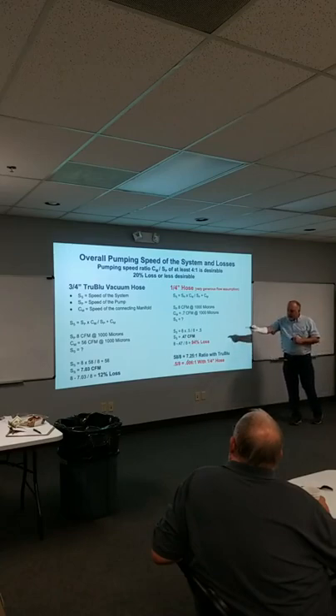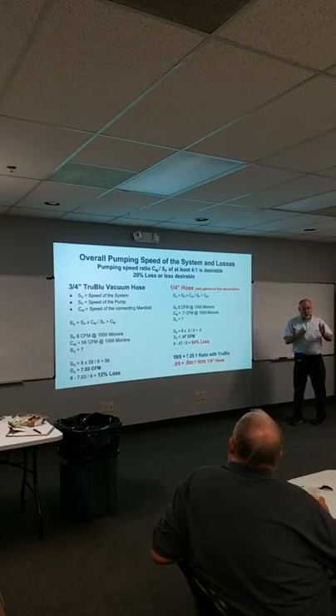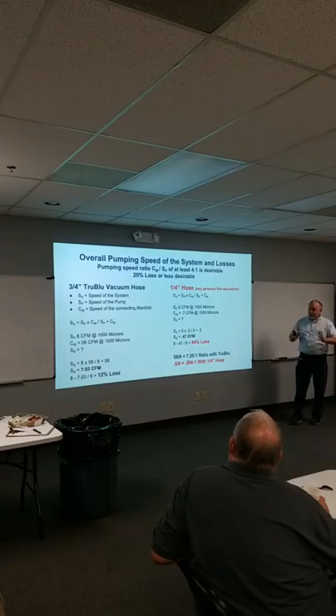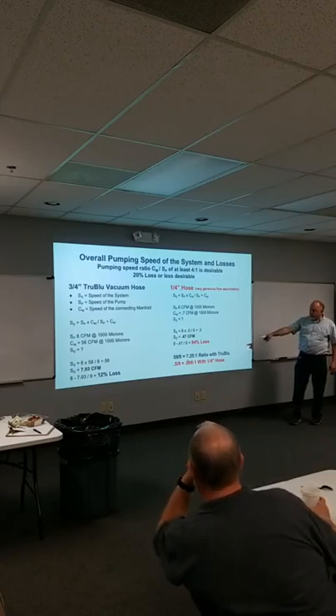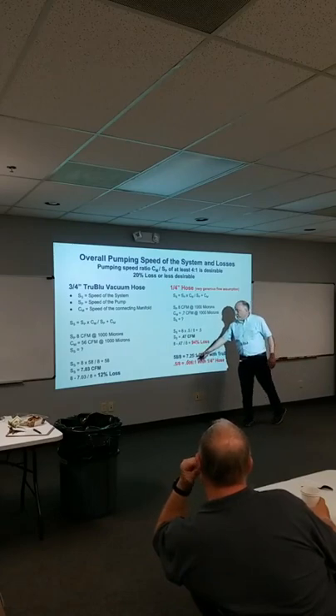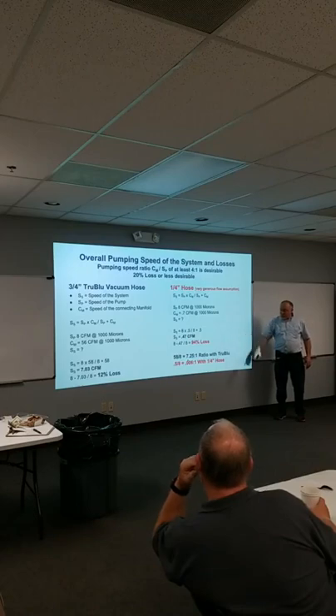Statistical formula. So basically, if we were to take a, and you want to have a pumping speed of at least 4 to 1, right? There's always a loss. As soon as you hook up a vacuum hose to a vacuum pump, there's a loss, period. Can't stop it. The pumps are all rated at free flow, okay? So that 8 CFM pump is 8 CFM at free flow. So down here, I just did the math here, and if I hook up, to an 8 CFM pump with a true blue hose, I have about a 12% loss, which sounds substantial, but that is a ratio of 7.25 to 1. So way over 4 to 1, right? 4 to 1 is desirable, but it's 58 to 8 ratio or 7.25 to 1.